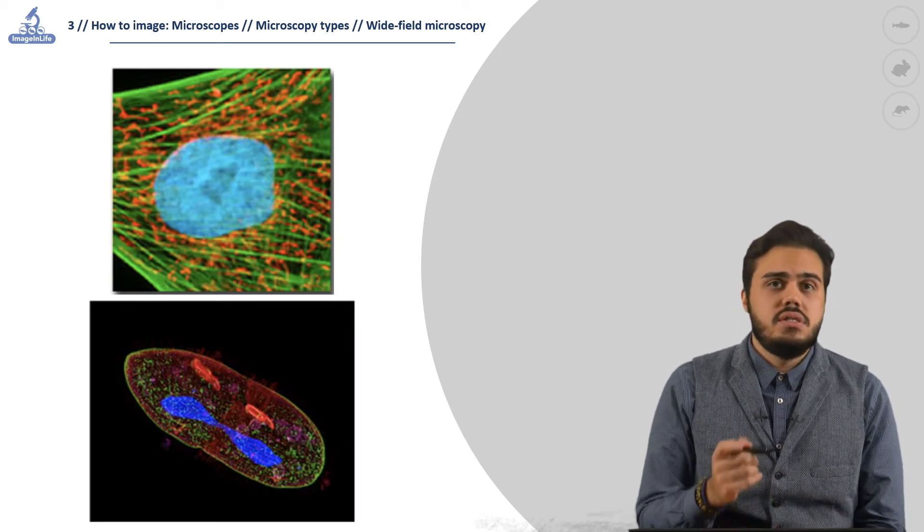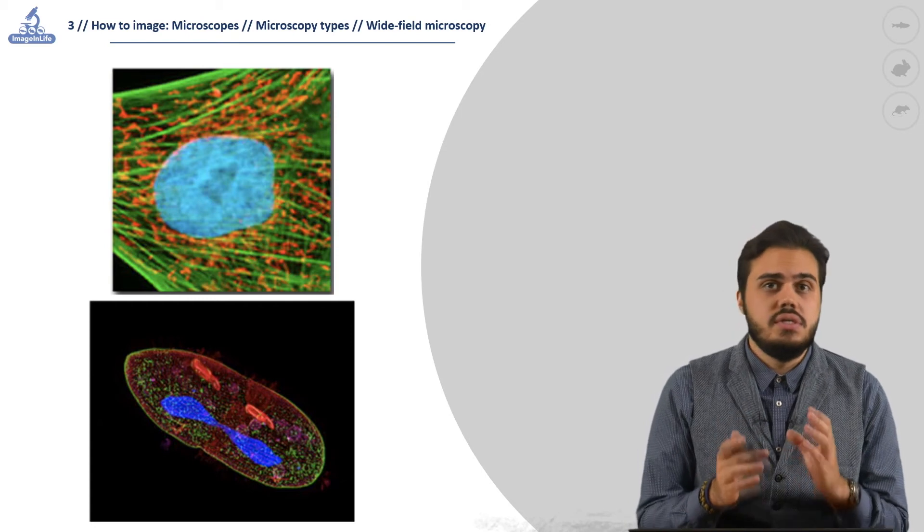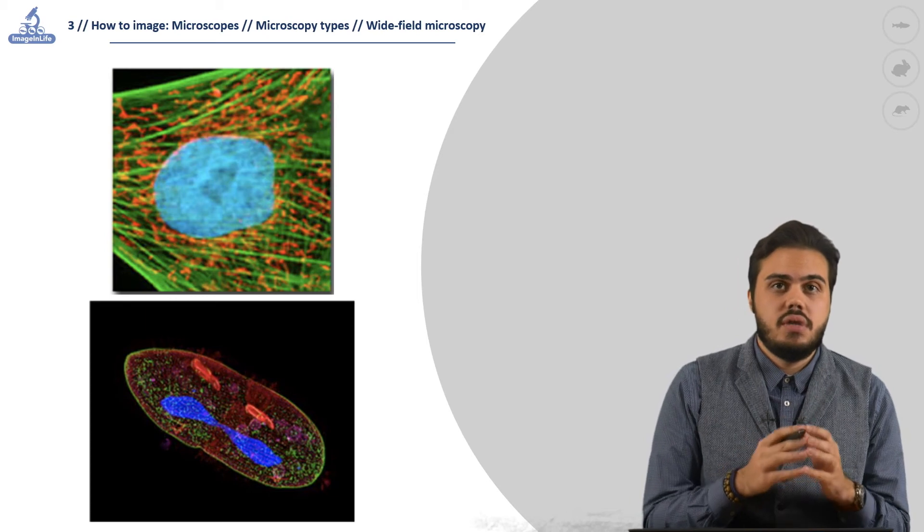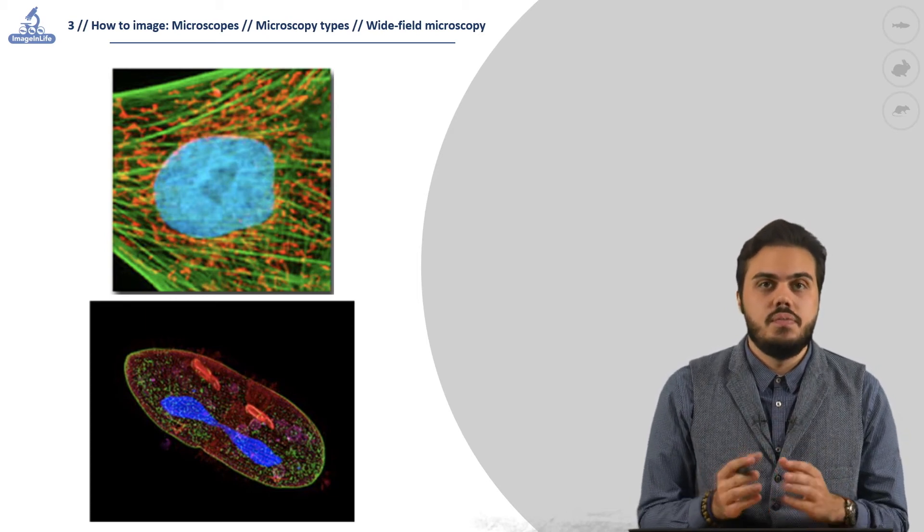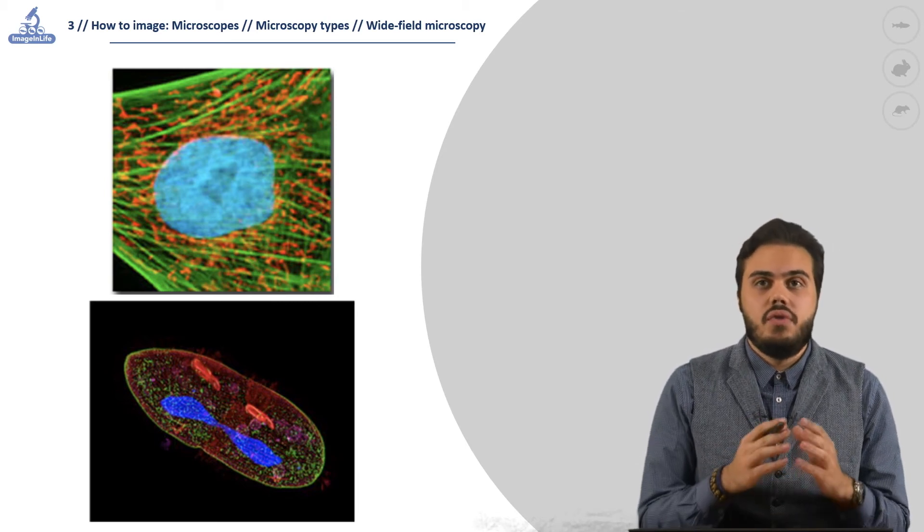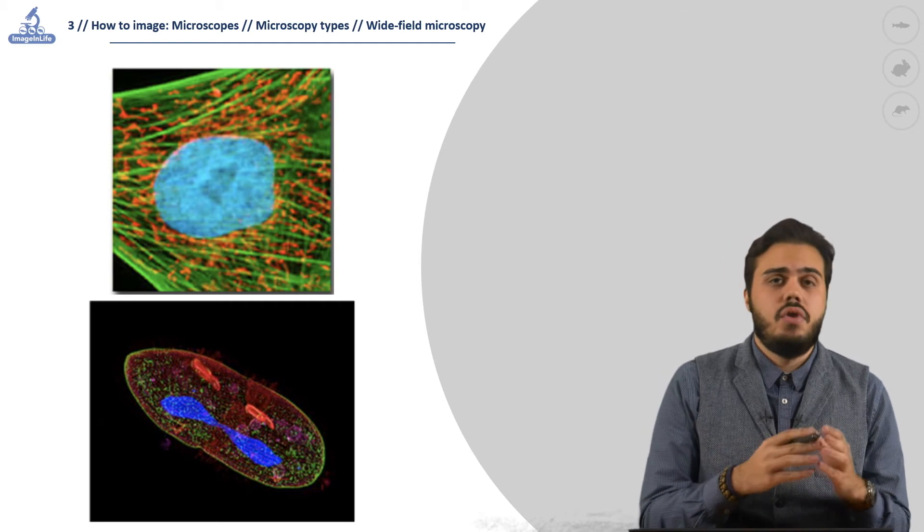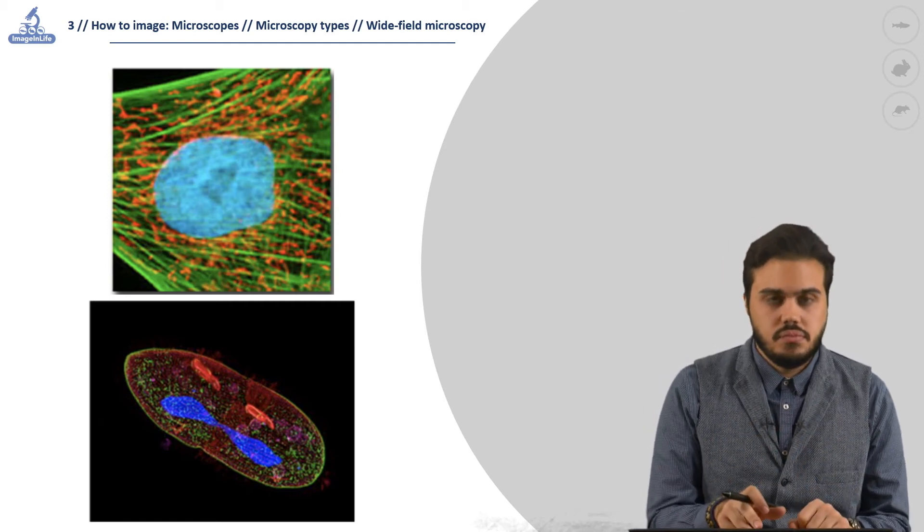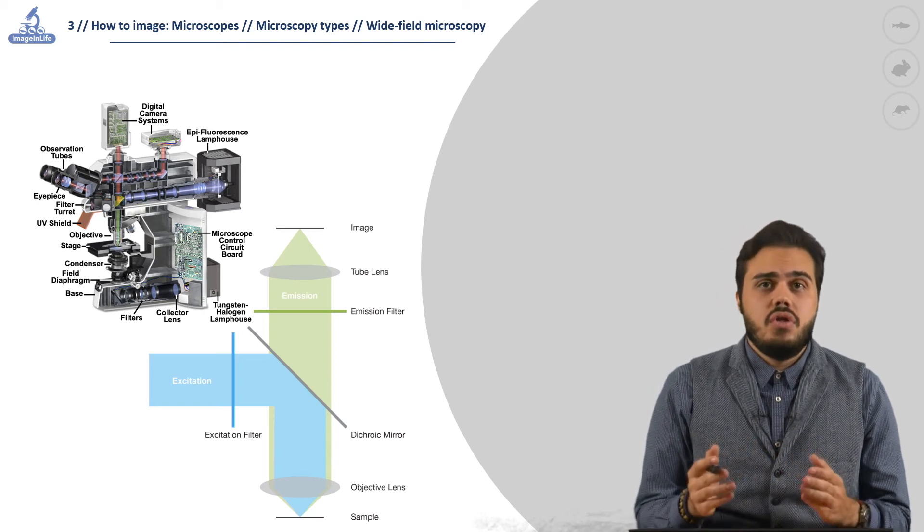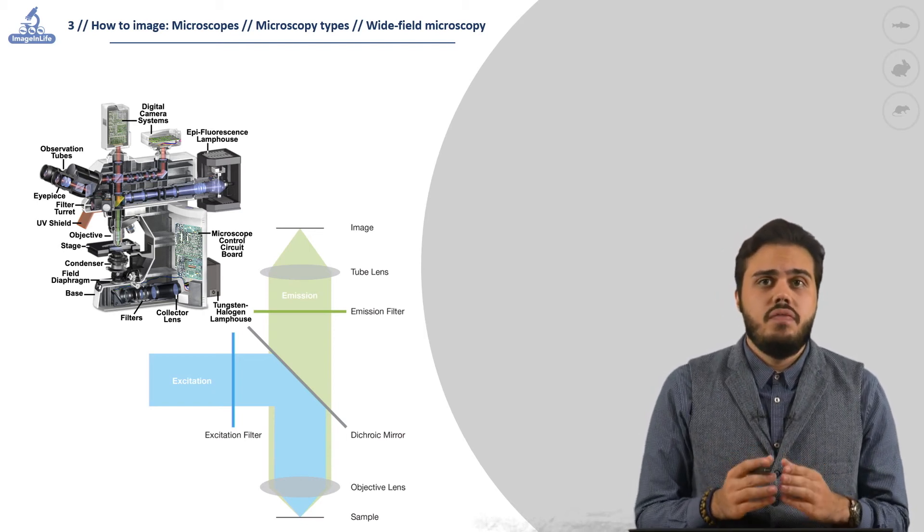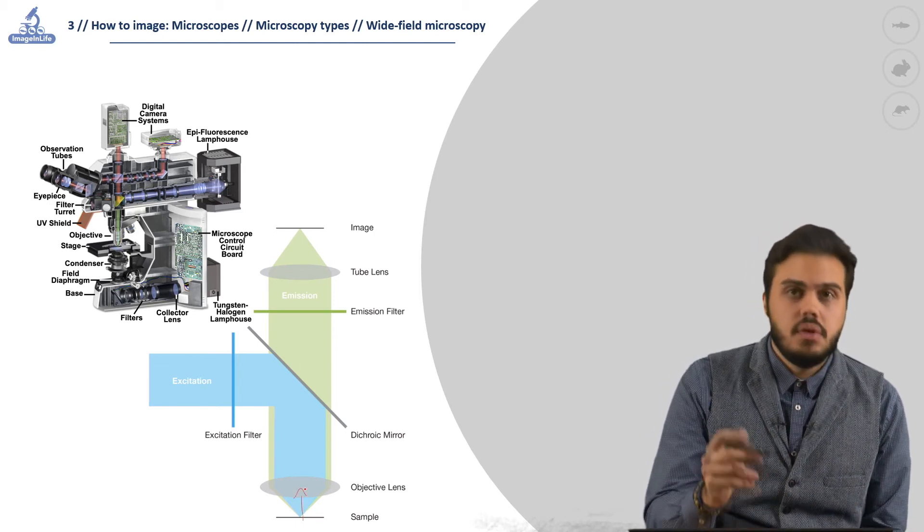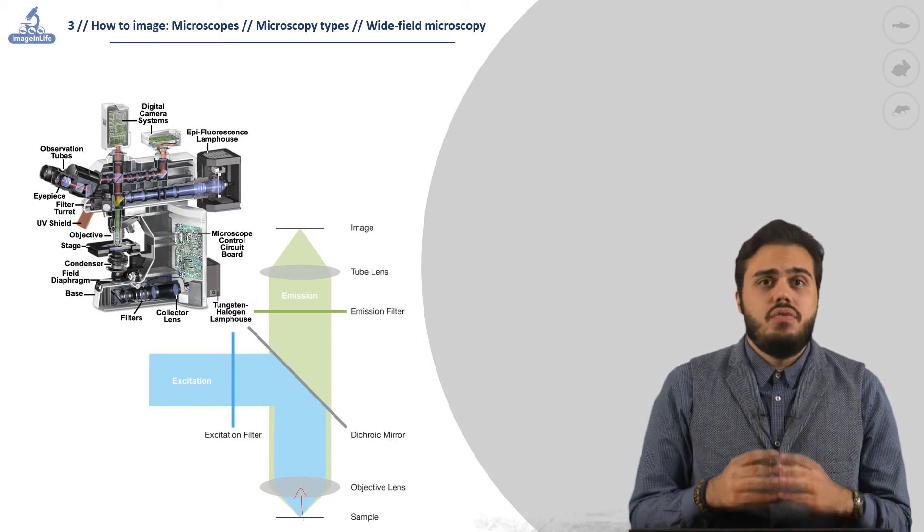Often it is necessary to observe specific structures inside the specimen itself, and one way to do this is to label a specific structure with fluorescent molecules. These molecules are excited by a specific wavelength of light and immediately re-emit light of a longer wavelength. In epifluorescent microscopy, the objective acts as a condenser, so it's always well aligned, increasing greatly the quality of the images.